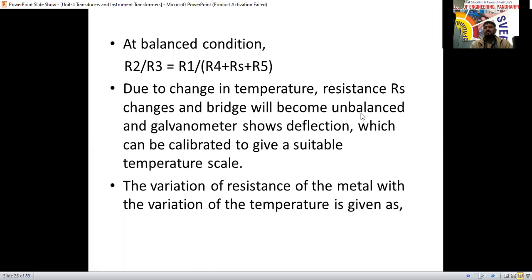Next, at balanced condition, all of you know the formula already. Here R1, R2, R3 are different, so the bridge arrangement is different. R2 by R3 equals R1 divided by the sum of R4, RS and R5. If it is balanced, the ratio of R2 and R3 equals the ratio of R1 and the summation of R4, RS and R5. These are known values, and R4 and R5 are the lead resistance values.